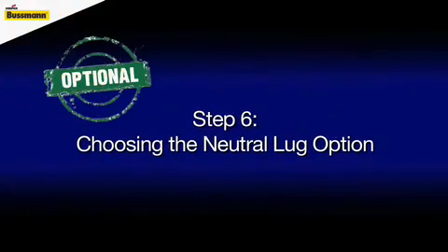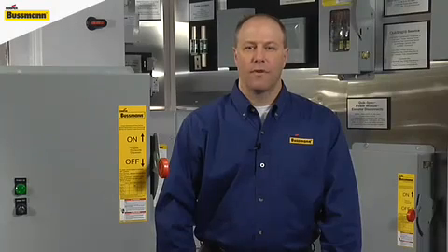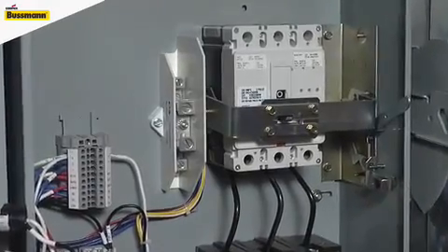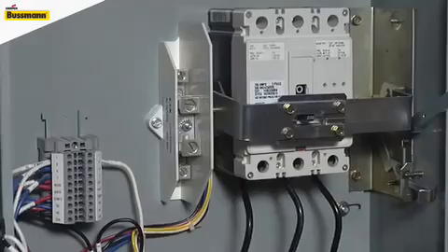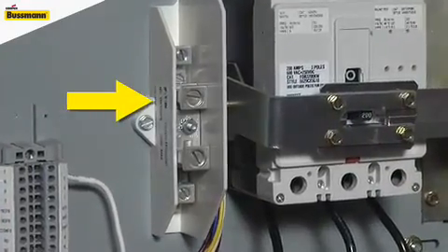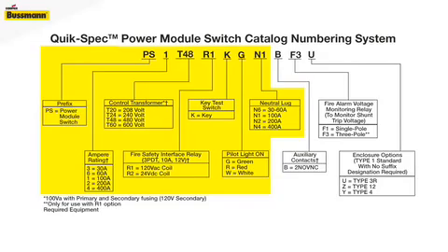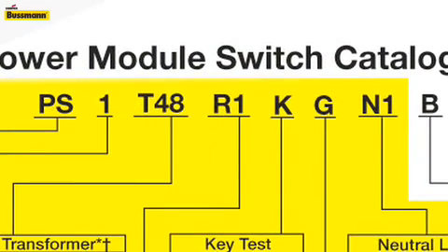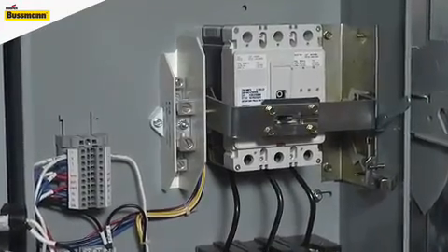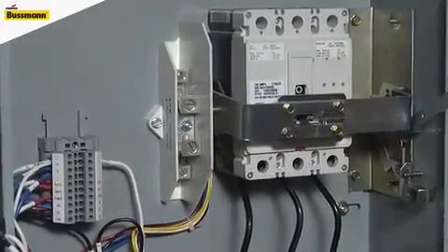Step six partly depends on your local code requirements for isolated neutral lug. We offer different options to match the load configuration of each power module. If your local code jurisdiction requires this feature, simply add the code that corresponds to the power module amperage chosen in step one. We specified 100 amps in our example, so we will need to add the N1 code to our part number sequence. If you are unsure and want to add this feature, this is a very inexpensive option.